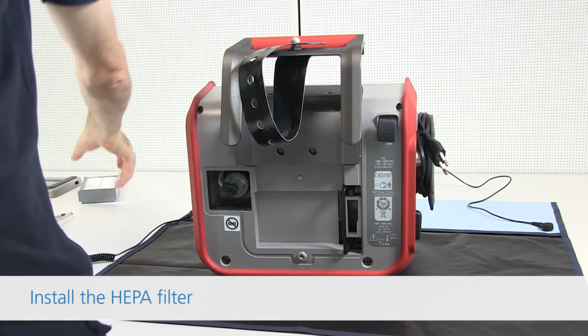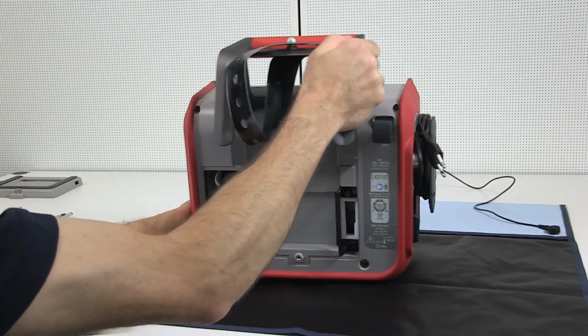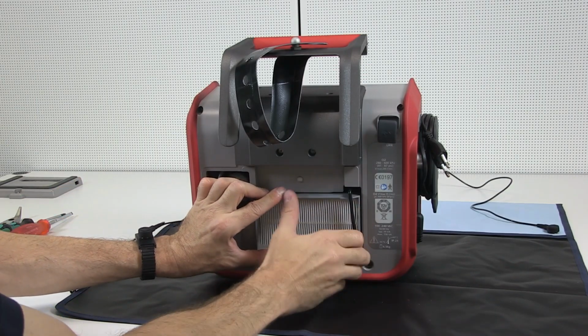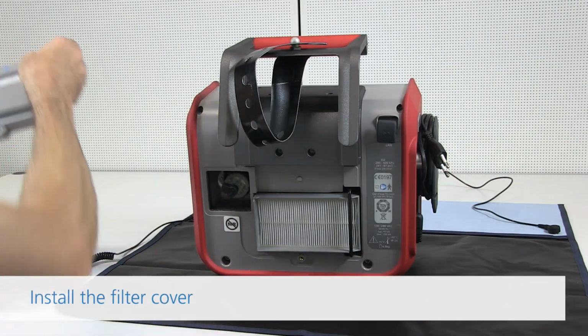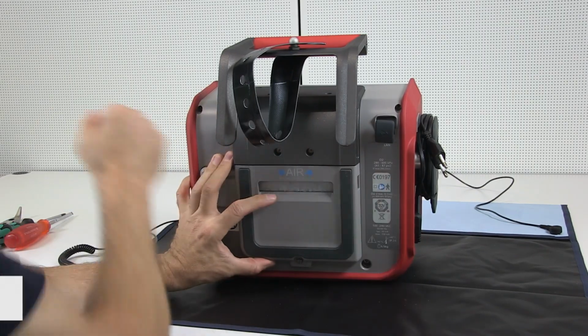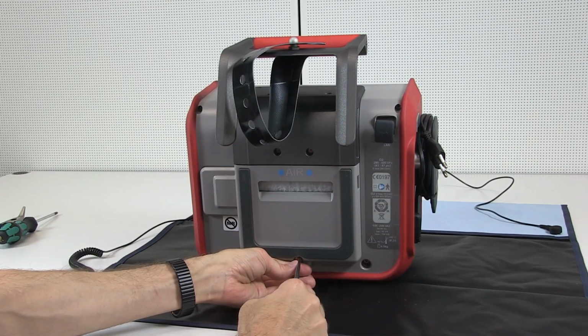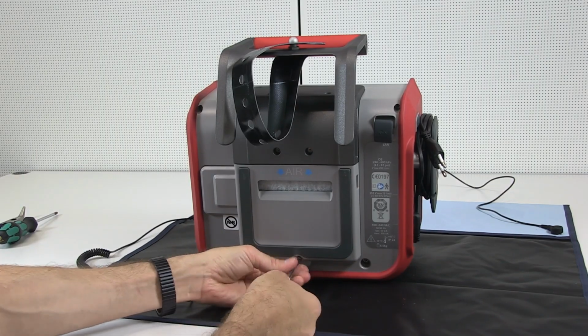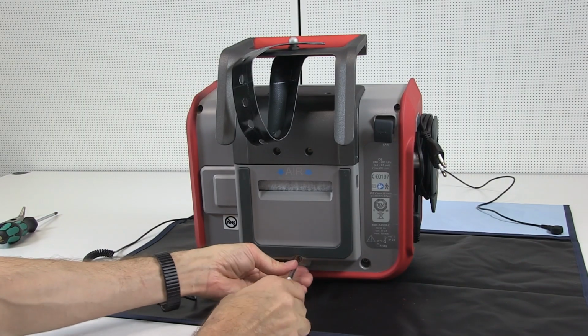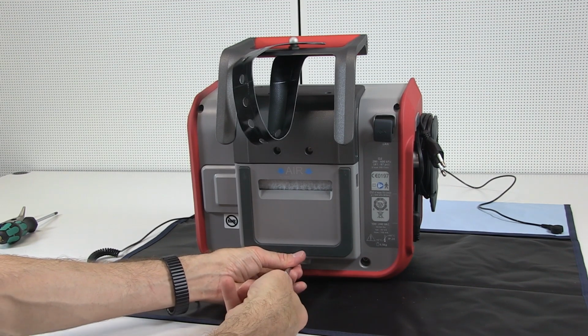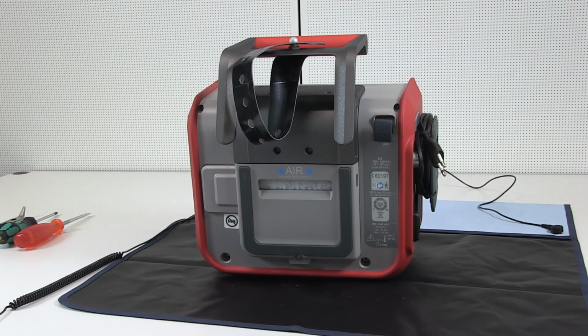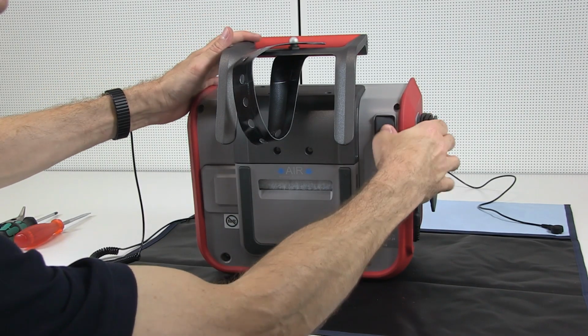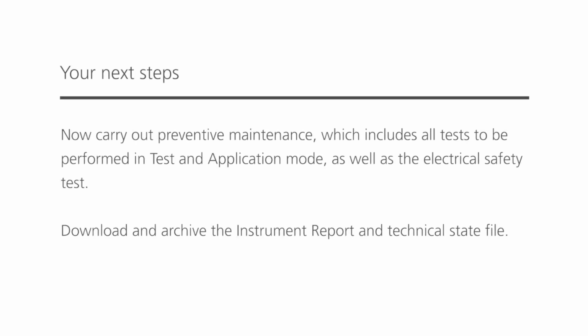Install the HEPA filter and the filter cover, then lock the captive screw. Your next step is to carry out preventive maintenance, which includes all the tests to be performed in test and application mode, as well as the electrical safety test. Finally, download and archive the instrument report and technical state file.